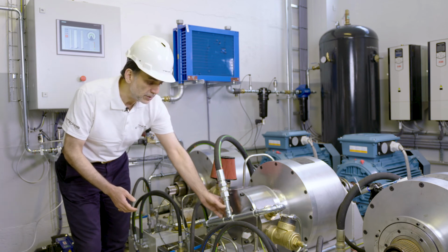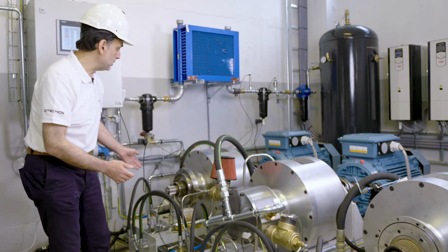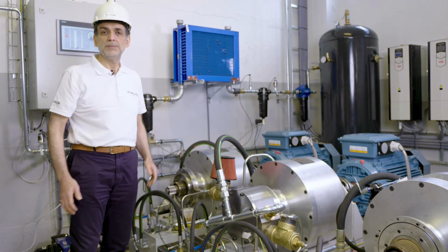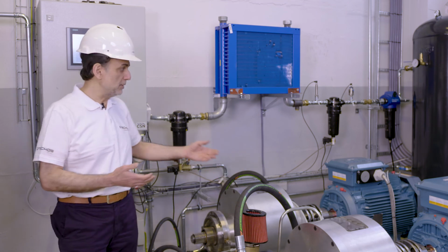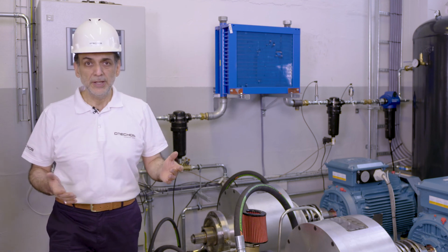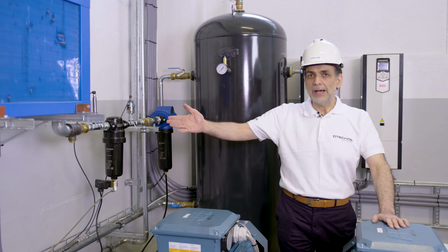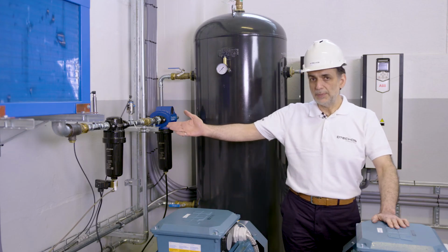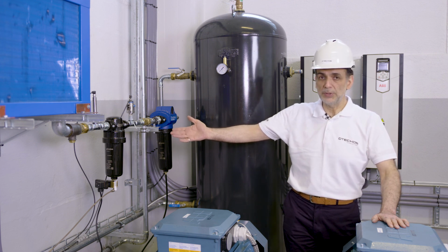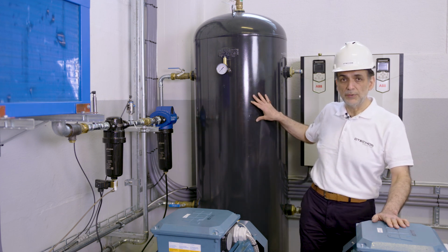The outlet of the process unit is connected through a system of pipes into the filter, cooling, and into a pressure vessel. The produced compressed air passes through a cyclone to separate any water condensate or liquid condensate, and then it is cooled by passing through a forced draft air cooler. After the air cooler, the compressed air passes through a secondary cyclone to further remove any liquid condensate. It is filtered and finally stored in a pressure vessel for use on demand.